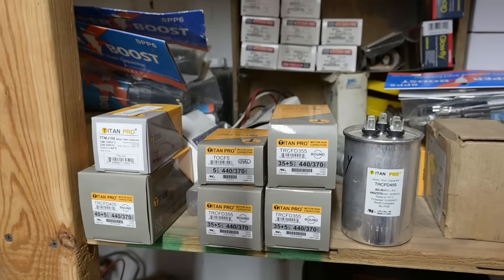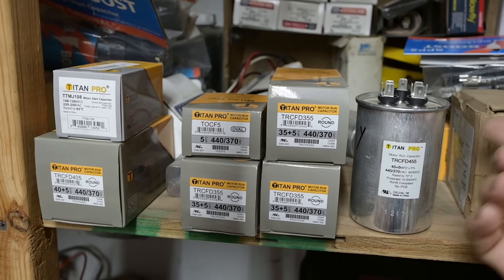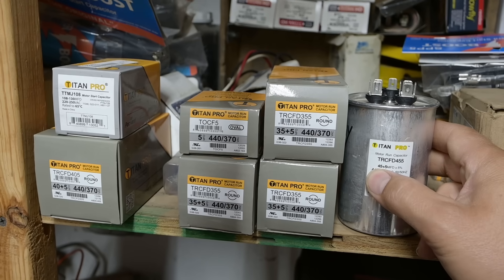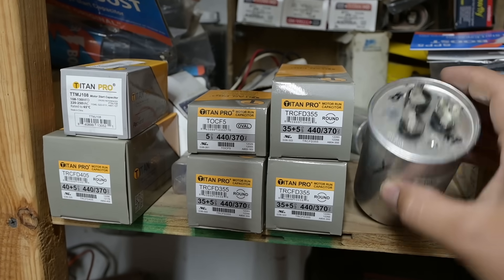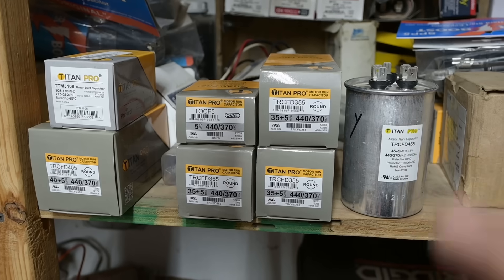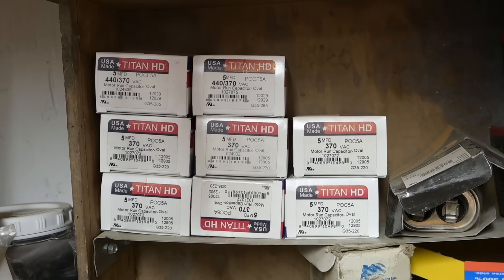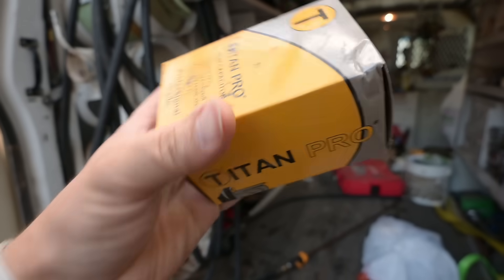Here in the parts room we have a few different capacitors to take a look at, but I actually don't see a 45/5 capacitor. That 45 is going to be a 45 microfarad capacitor for the compressor at the HERM terminal, and a 5 microfarad capacitor for the fan terminal — so it's technically called a dual capacitor, two capacitors in one. If you have just a single capacitor it's not going to have that dual rating. Most of those individual ones up there are 5 microfarad capacitors.